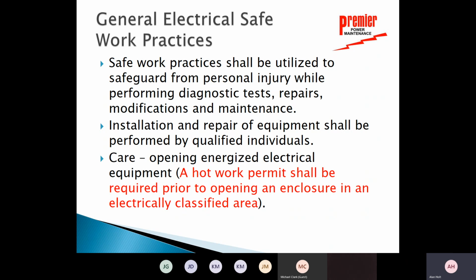Then we need to have care when we're opening energized electrical equipment panels. So we need to understand that in certain areas, if it's called an electrically classified area, before you can open an energized piece of equipment, just open the door, if it's energized behind that, that would require a hot work permit. The hot work permit is much different than the energized work permit, but it is a permitting process that you would have to go through with Marathon in order to open a panel door with energized equipment in it if it was in a special area, an electrically classified area, where there could be explosive or flammable atmosphere available to us.